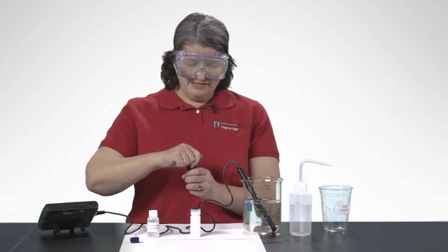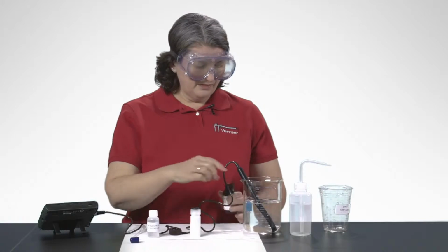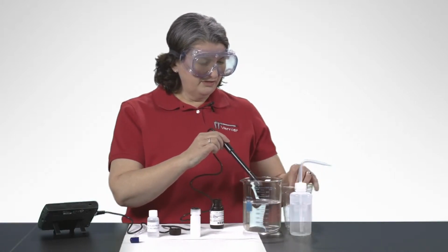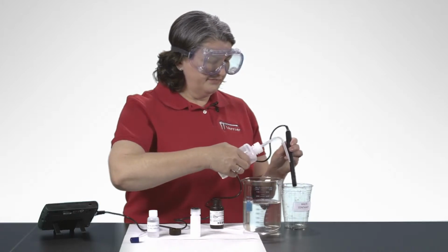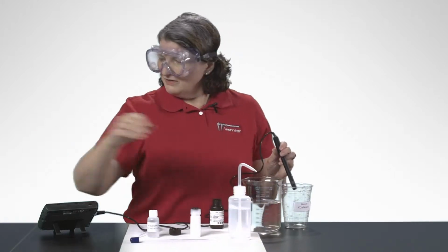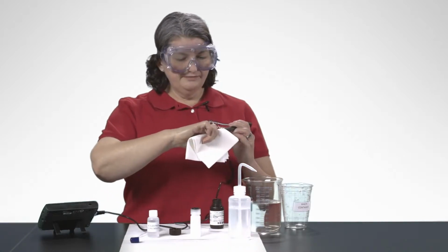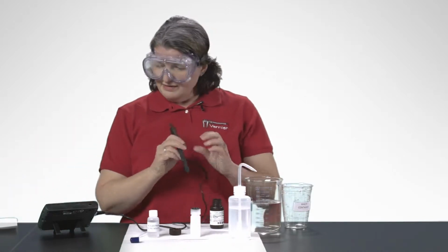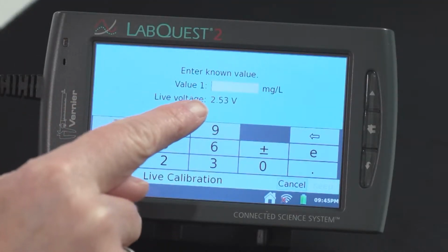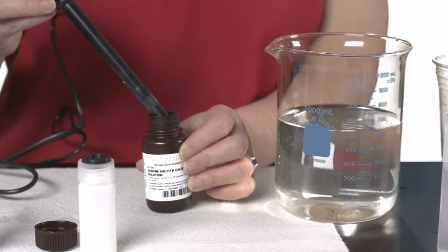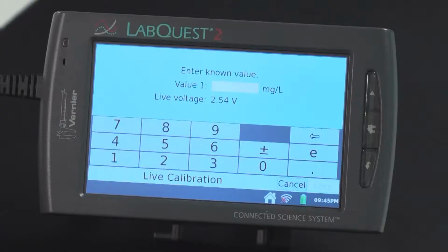So what I'm going to do is get this opened, take the probe out, rinse it off a little bit because that was our stream water. Dry that very gently on the sides with a paper towel. Now I want you to notice this live voltage being displayed here. It's probably going to be up over 2 volts at this point, but once I put it in the sodium sulfite, okay, and all you need to put in is the very tip in this case, watch what's happening to the voltage. It's dropping, and it's usually going to go down to between 0.2 and 0.4. That tells you things are working properly.